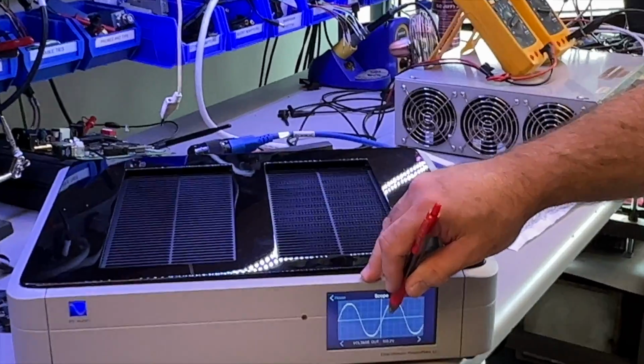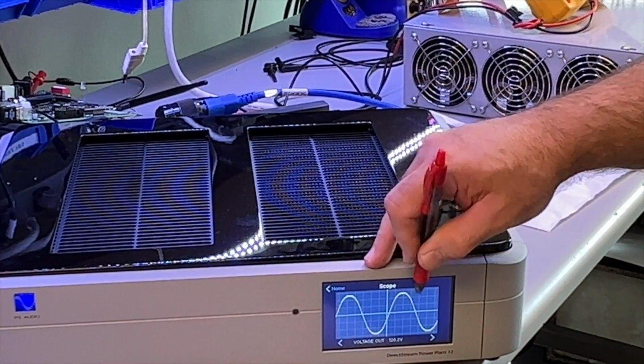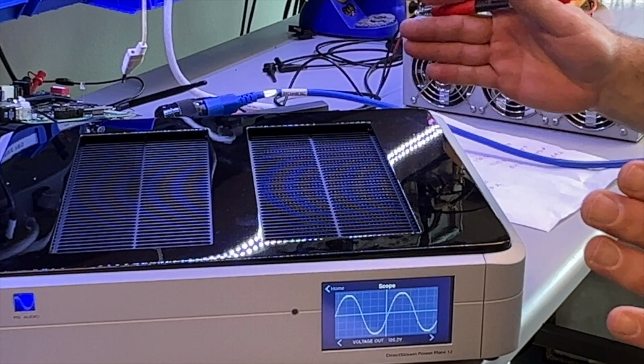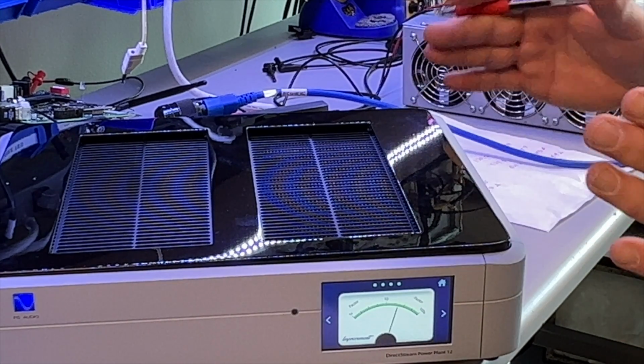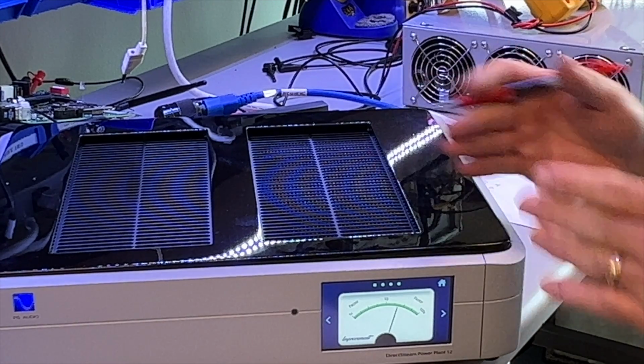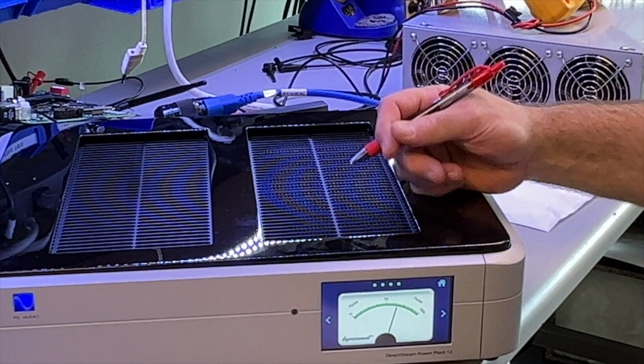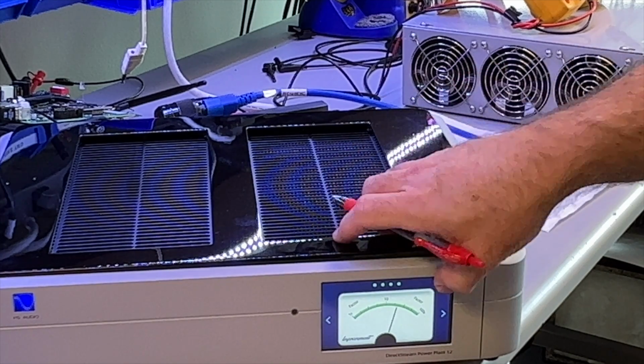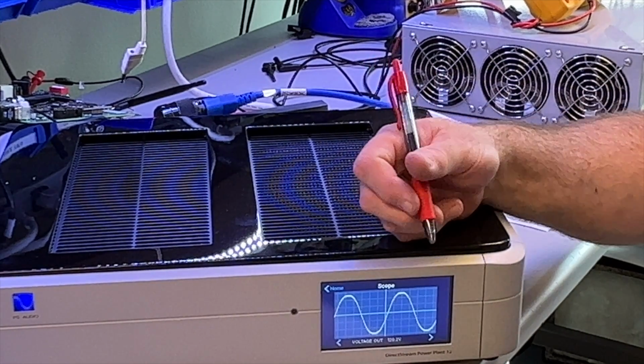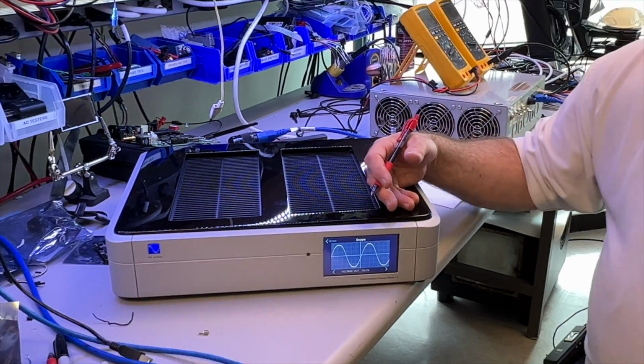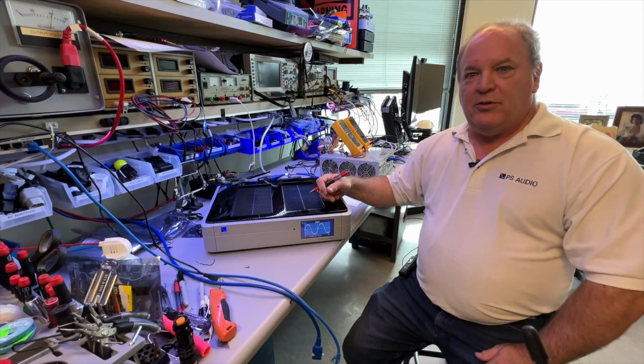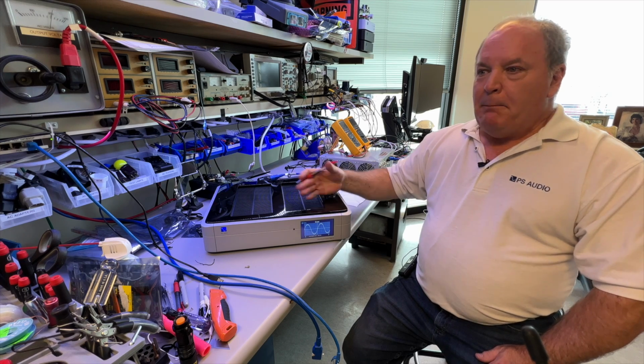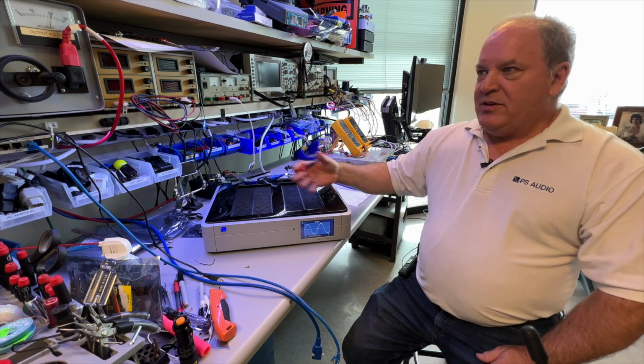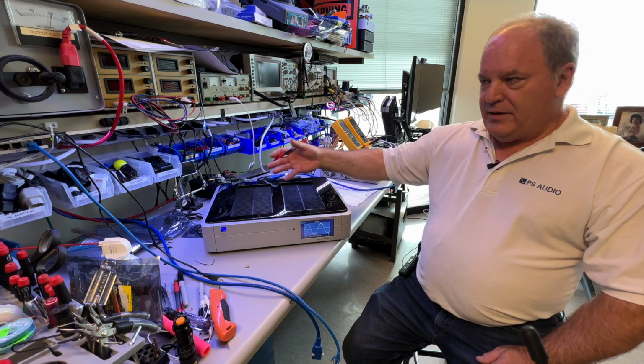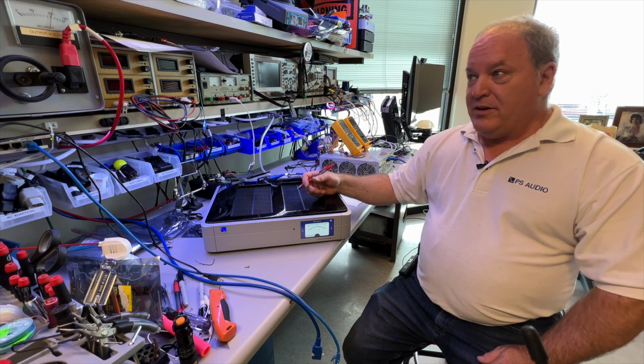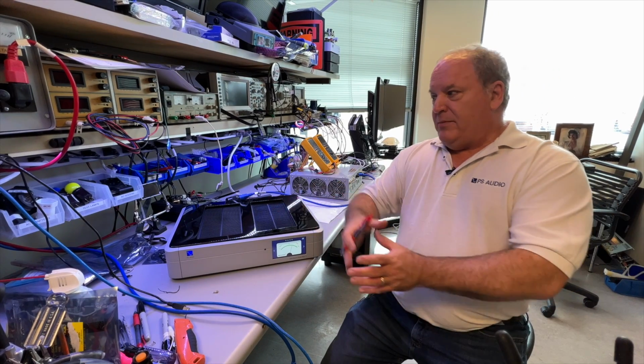So by adding third harmonic of the 60 or 50 hertz, we round off this top a little bit, and now it's got a wider pulse, a longer amount of time that the power supply can deliver power into the capacitors. So if I deliver half the current for twice the time, the same amount of power goes into the power supply. The power supply's happy. But all the losses in a piece of equipment, the resistance of the transformer and things like that - especially the transformer - is probably the biggest impedance between your power supply capacitors and the wall.